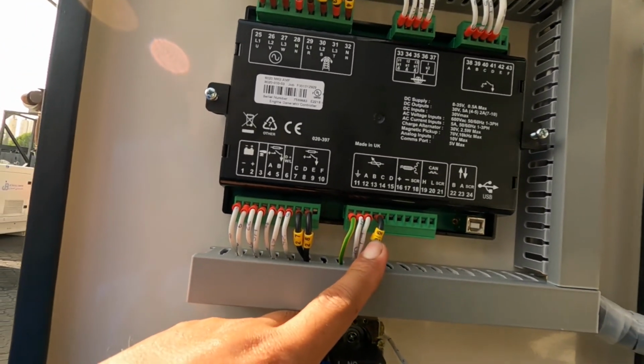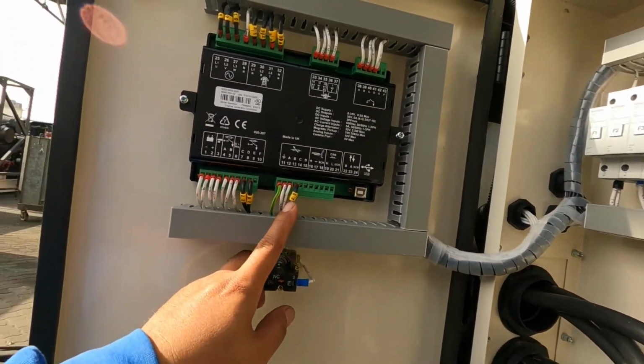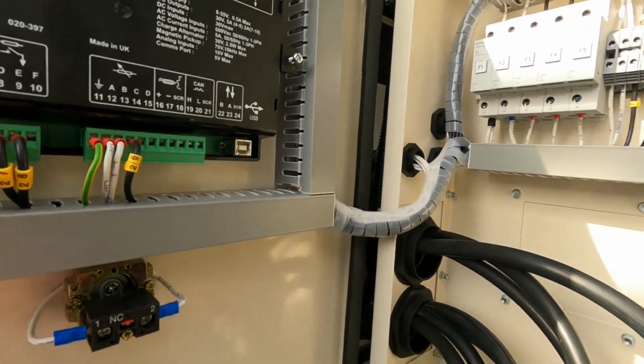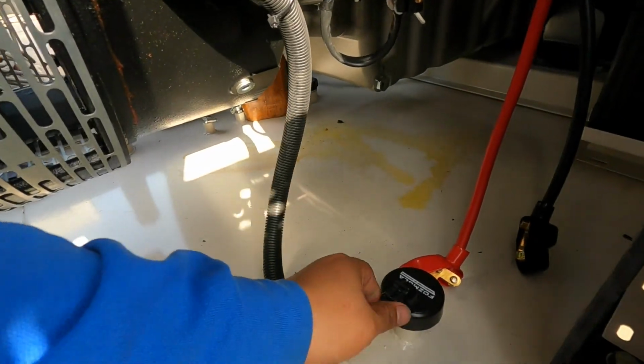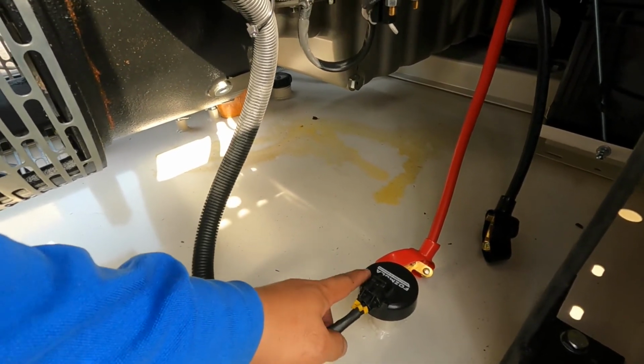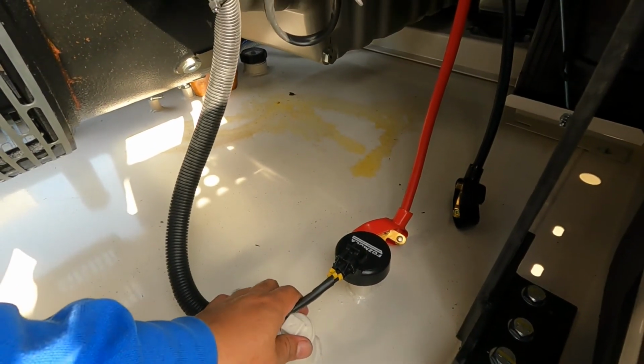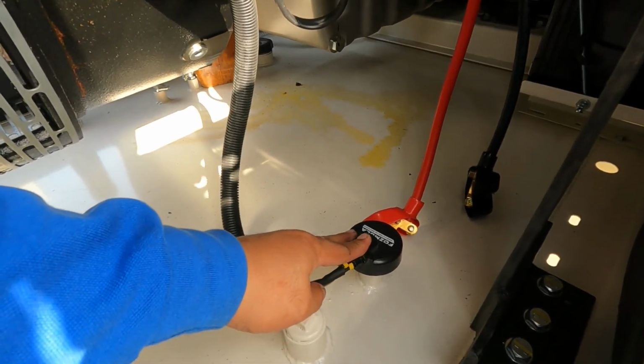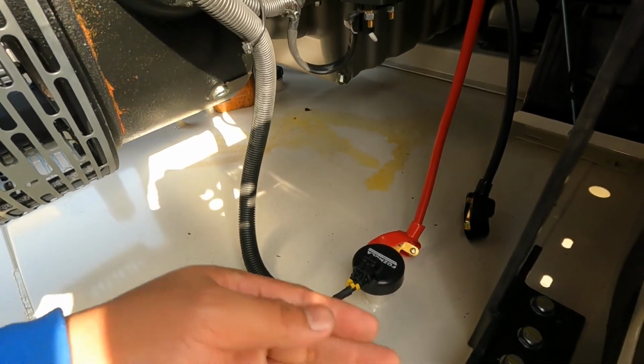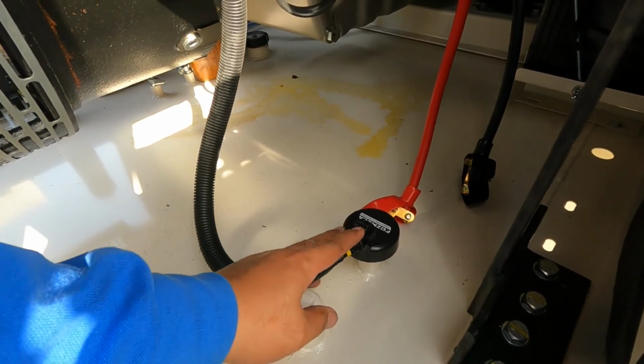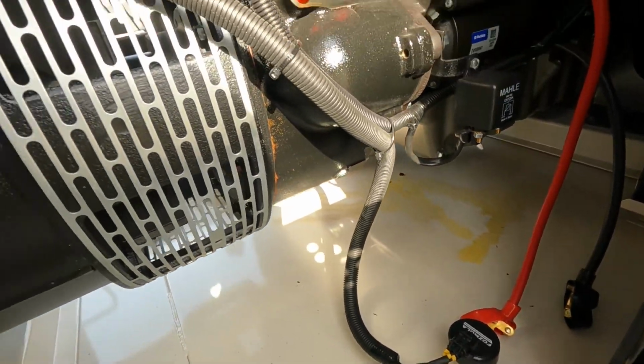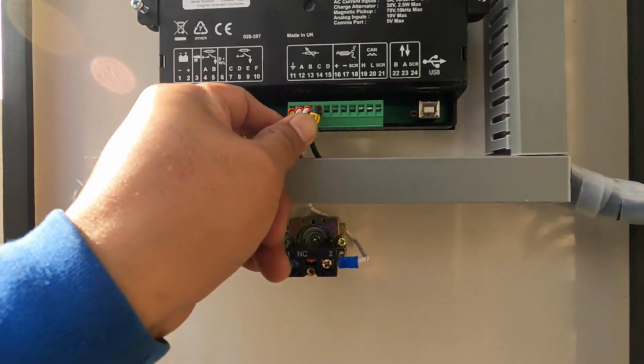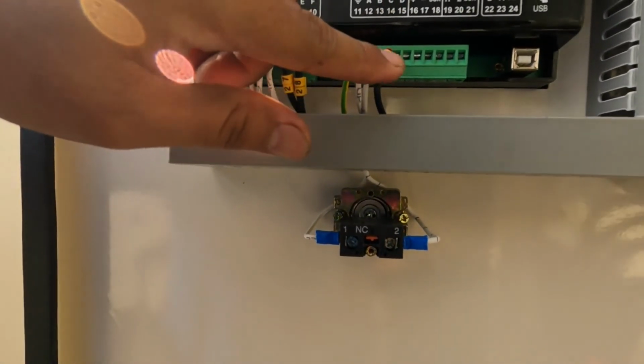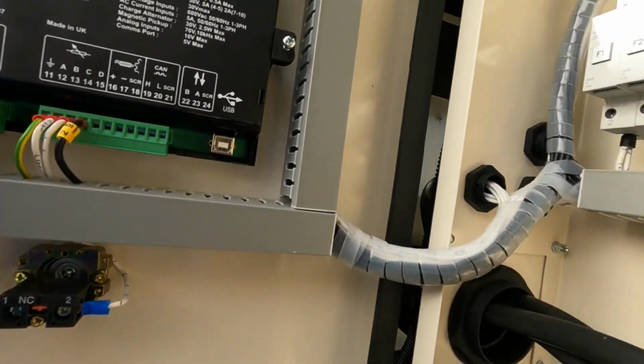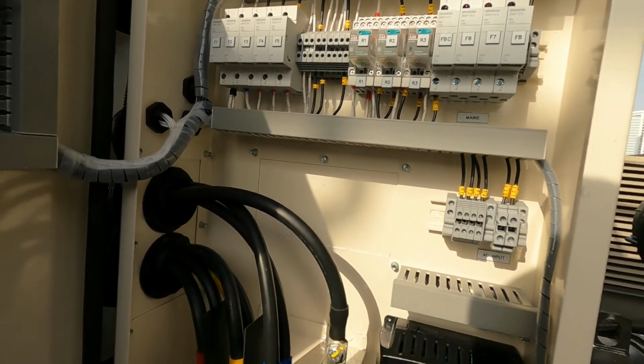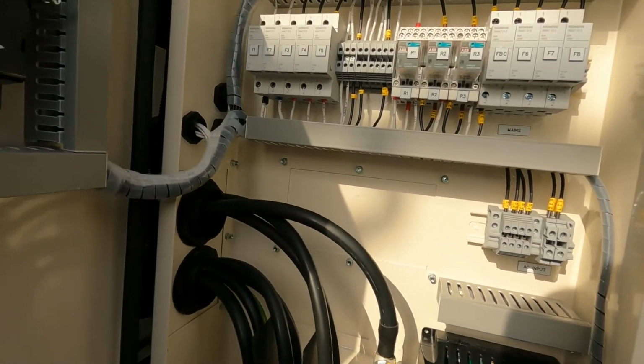This is for the fuel connections and for your fuel sensor. It is connected from here. This is the fuel sensor input, and this gives you the percentage of your fuel. Make sure you install the program correctly, depending on what sensor you are using. You have to search the options for your sensor in the program. It is connected from terminal number 14, which is designated for the fuel sensor. The rest is only standard, and here is the battery charger, and this is all the wiring for that.